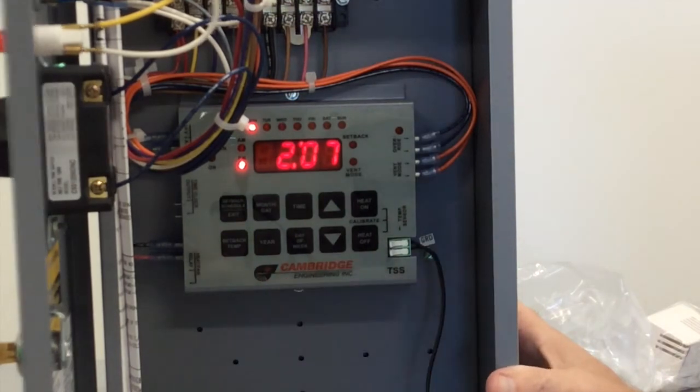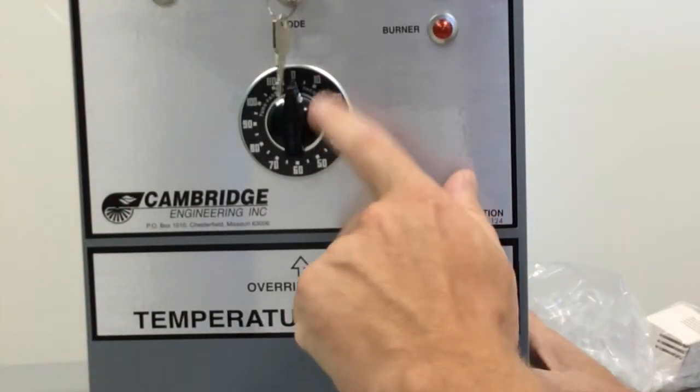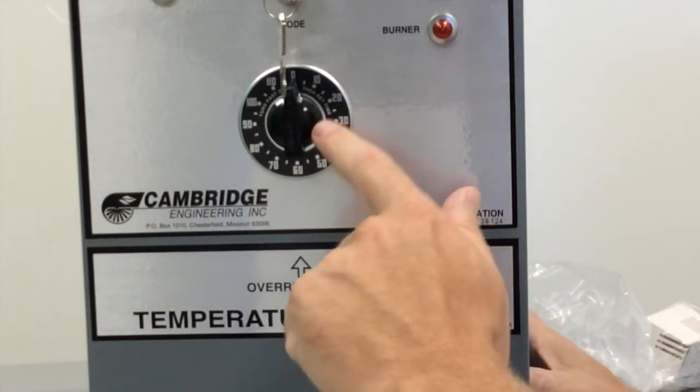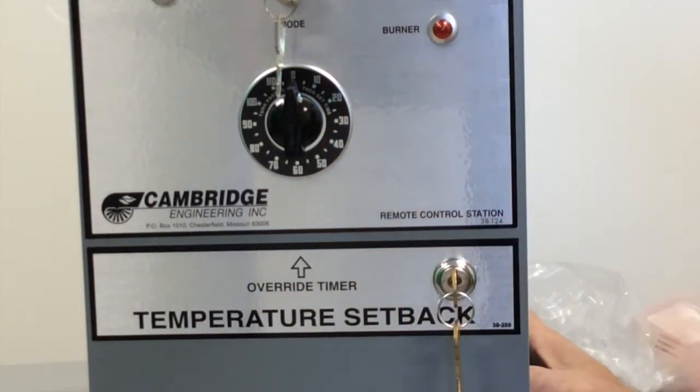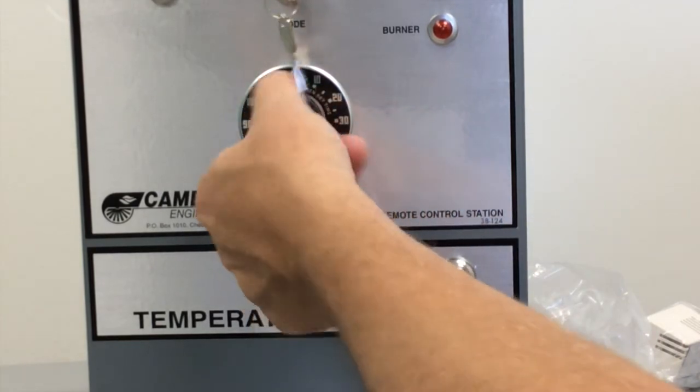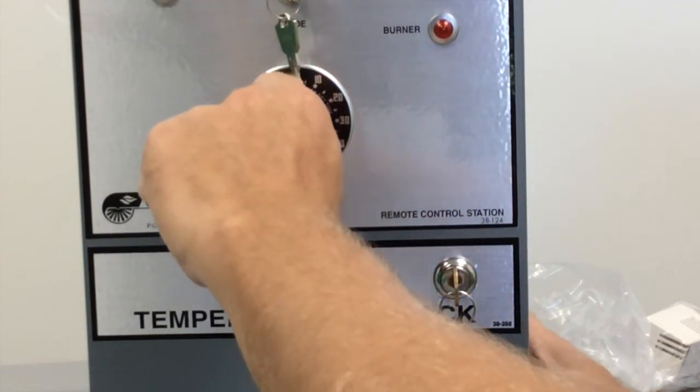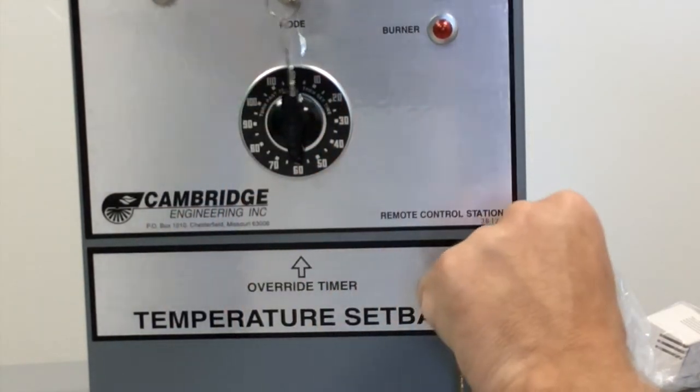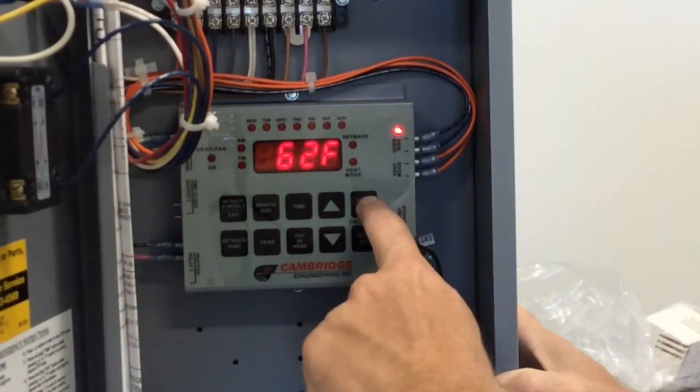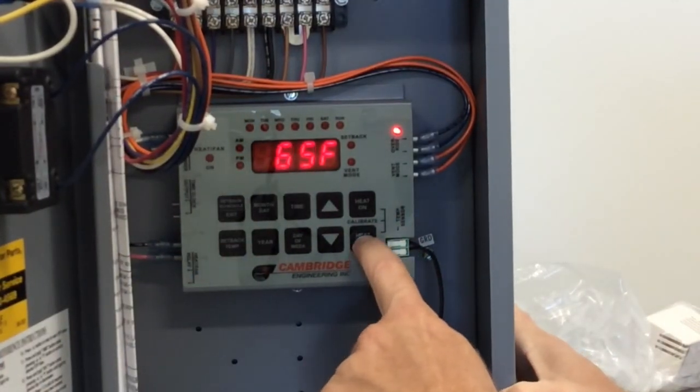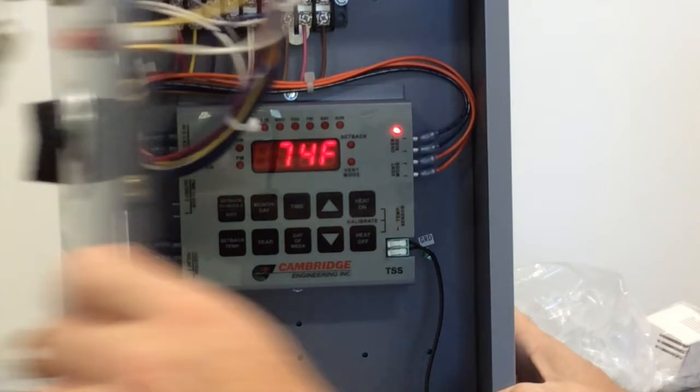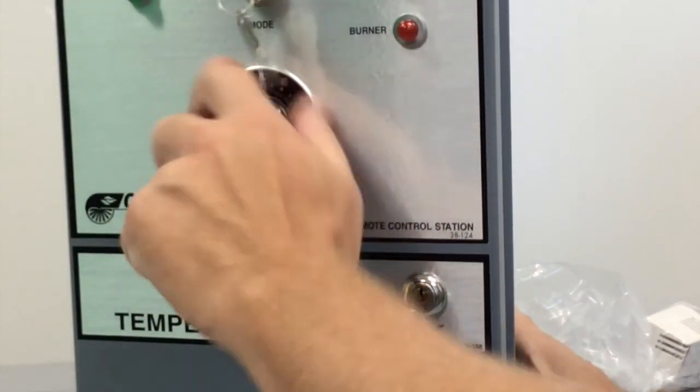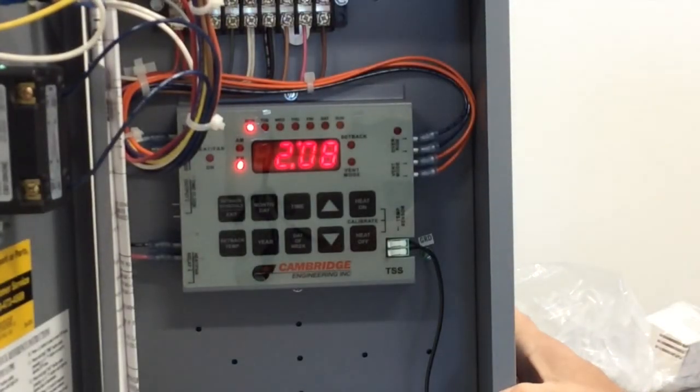Now once again, when you're in the occupied mode, this override timer will do nothing for you. A lot of folks believe that the override timer forces the heater on no matter what. That is not the case. Whenever you turn this override timer, let's just say, for instance, here this is one hour, it's going to bring you back to your 62, 65 until the timer expires. Then once the timer expires, it puts you back into your setback mode.